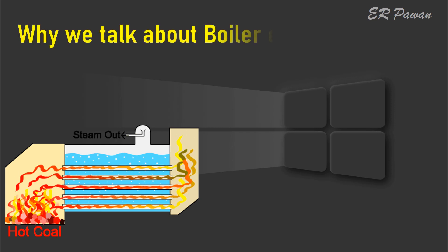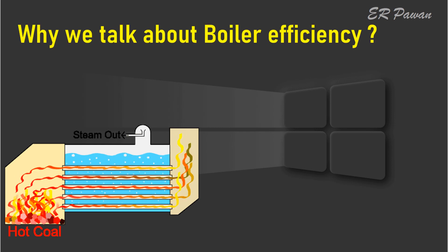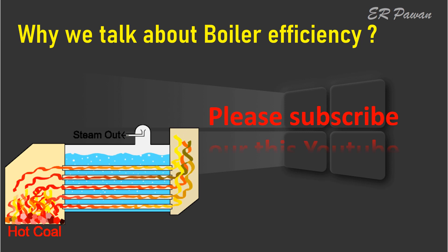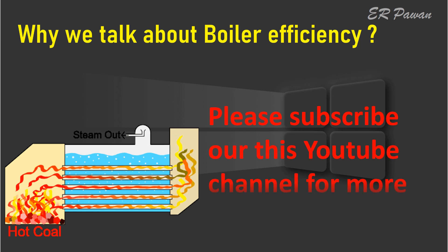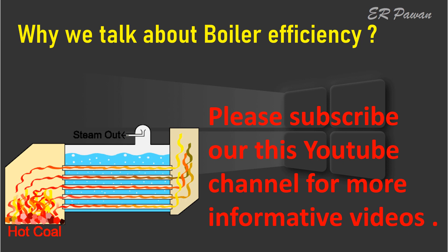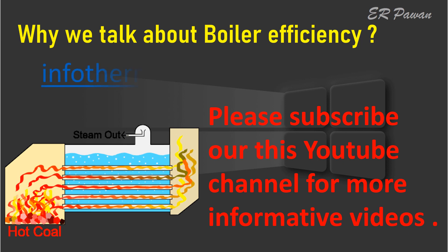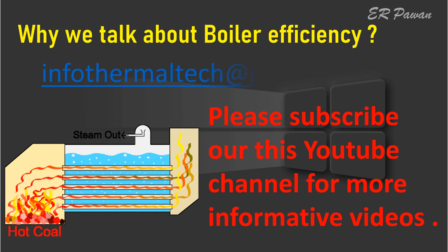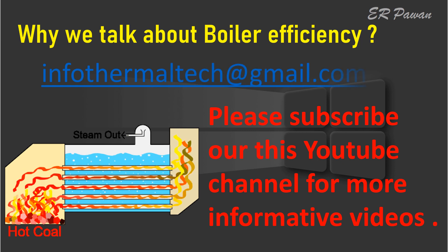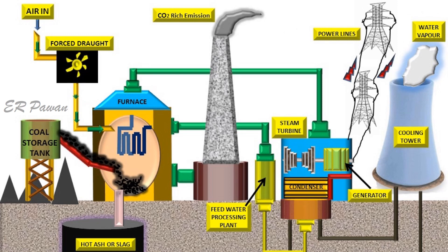Why do we talk about boiler efficiency? Boiler efficiency is a measure of how effectively chemical energy in fuel is converted into heat energy and steam going to the turbines. The largest boiler efficiency loss is sensible heat lost as hot flue gases and ash exit the boiler.